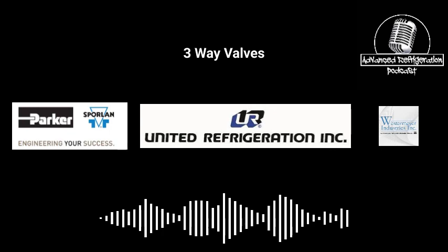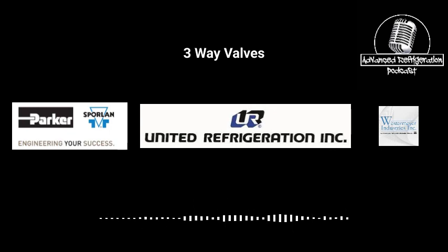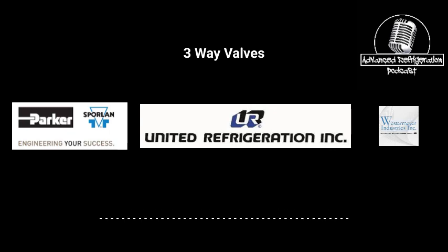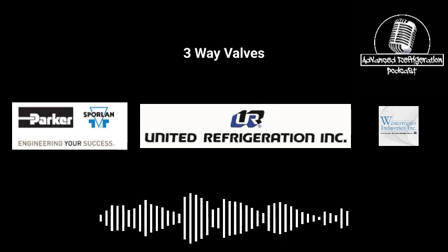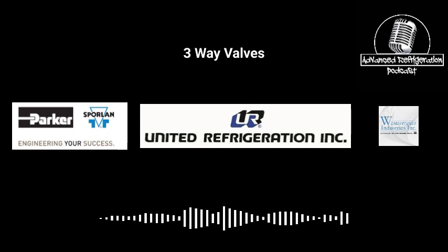So most of the three-way valves you guys are going to see are pilot-driven valves. A pilot-driven valve is using high-pressure gas from a discharge or liquid, and it is shifting a piston in that valve one way or the other by allowing gas to go into a chamber and push a piston down.